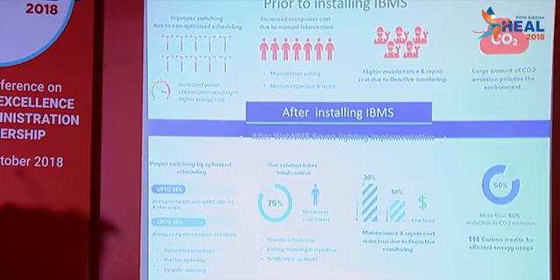So in a nutshell, you see here, this is prior to installing the building management system, and this is after installing. Here, improper switching due to non-optimized scheduling; proper switching by optimized scheduling, and energy saved is roughly 30 to 35%. Increased manpower cost due to manual intervention; here our solution takes total control, no manpower running around. Higher maintenance and repair cost due to reactive monitoring; here maintenance and repair cost reduction due to proactive monitoring. Large amount of CO2 emission pollutes the environment; more than 50% reduction in CO2 emission. So these are the advantages of IBMS.